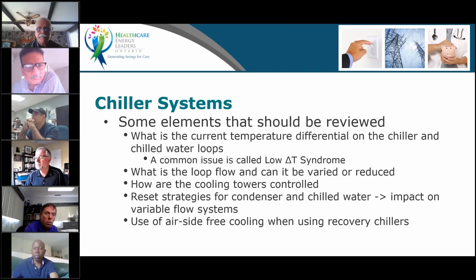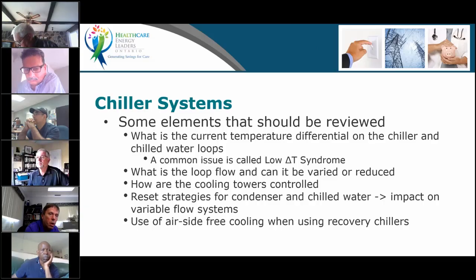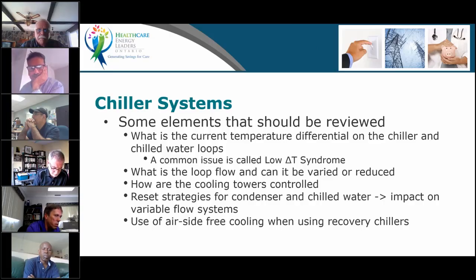Things that need to be reviewed when you have your chiller system. Look at the delta T, for example, on your loop. If you've got, let's say on the secondary loop here, 2 or 3 degrees Celsius, or sometimes even 2 or 3 degrees Fahrenheit delta T, you may have an issue of over pumping. You can do a pump test. That's a test we do often in recommissioning to establish what is the actual flow in there. And you may be able to adjust.